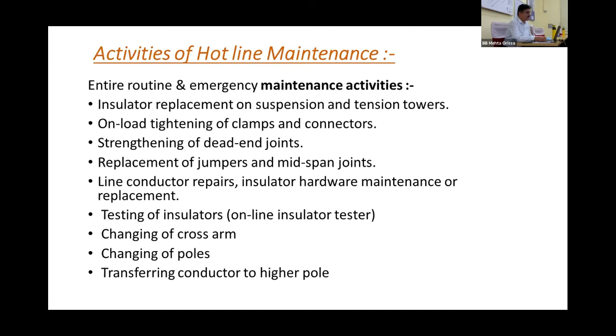Sir, a very important and mostly used method is the hot stick or live line tool method. These hot sticks are used in live line work by having the worker remain at a specified distance. We have a chart giving the specified distance for each voltage level, and the work is carried out by means of an insulating stick, which creates significant impedance between the worker and the live equipment so that hazard doesn't take place.